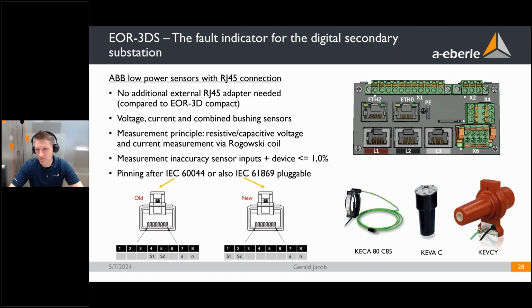Because these sensors of ABB have been on the market for a long time, at first they were according to the standard IEC 60044, and the pinning was a little bit different. Here, the current pins were on pins 4 and 5. Now they have changed to the new standard, 61869. And in this new standard, the pinning of the current has unfortunately changed. So the current is now on pins 1 and 2.